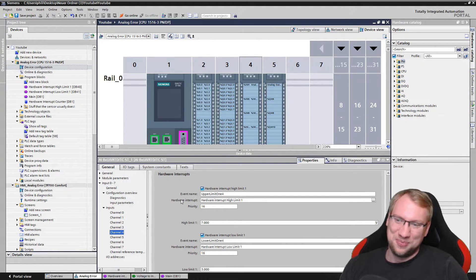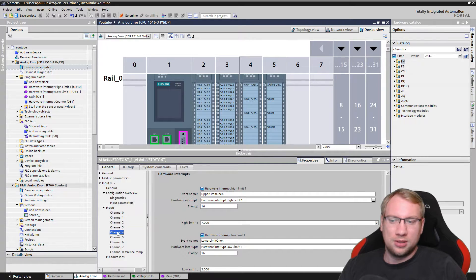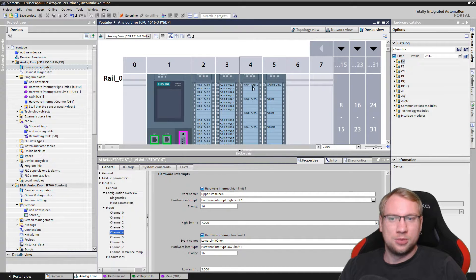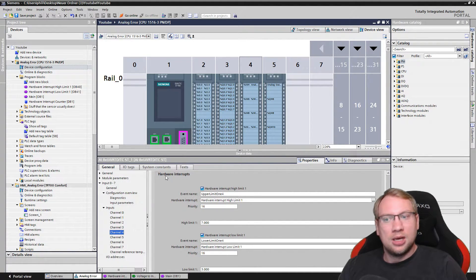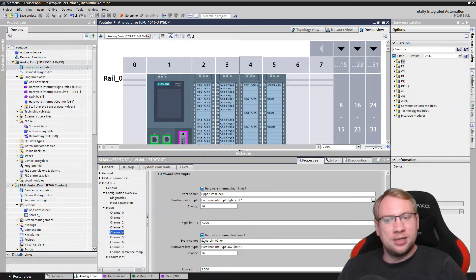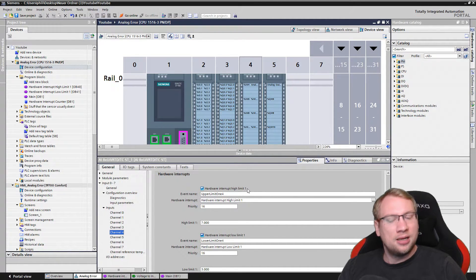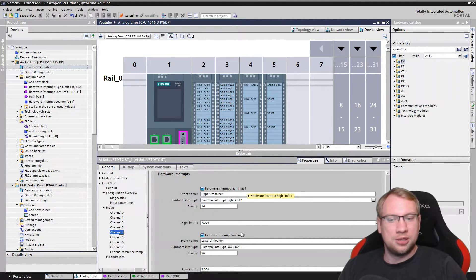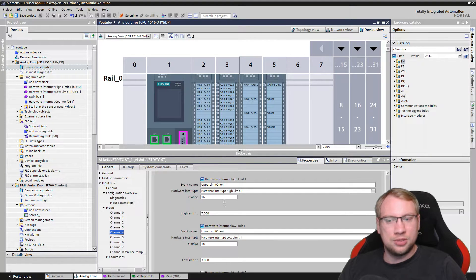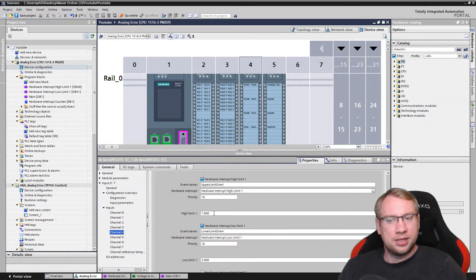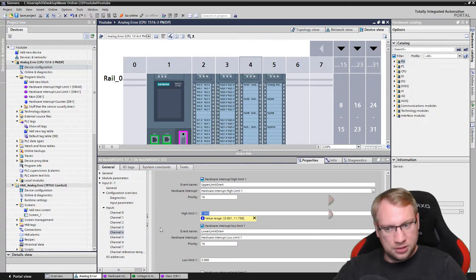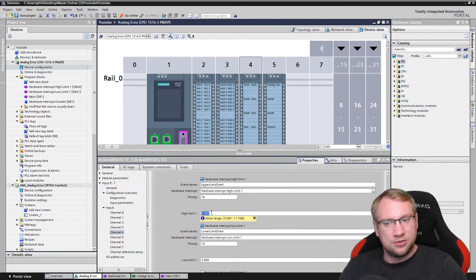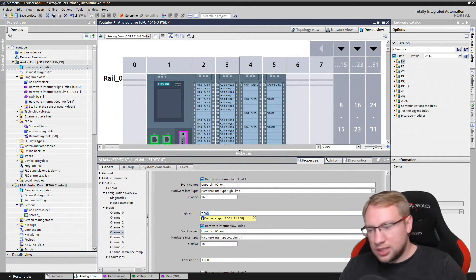Here on channel 4 that I have selected, which is the top right one here where my sensor is, I have already enabled two hardware interrupts: hardware interrupt high limit one and hardware interrupt low limit one. You see the high limit one should activate when we are going above 7.000 volts. I could also say 7.03 volts. Now it would react exactly on that voltage.